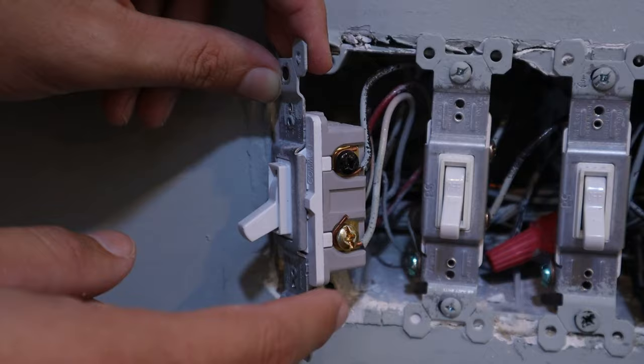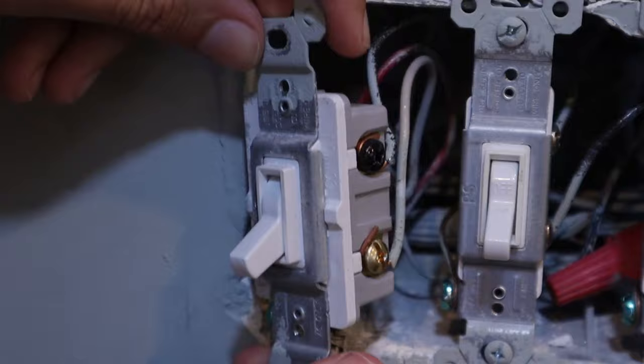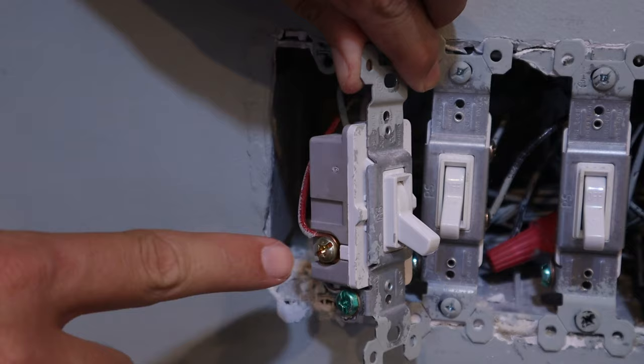Now, that means that then this one down below is a traveler wire, which I see the electrician did not get that tucked in all the way, which that is not good. So we're going to fix that in just a moment. And then if you switch it over here to the other side, you'll see this red wire. This is also a traveler wire.